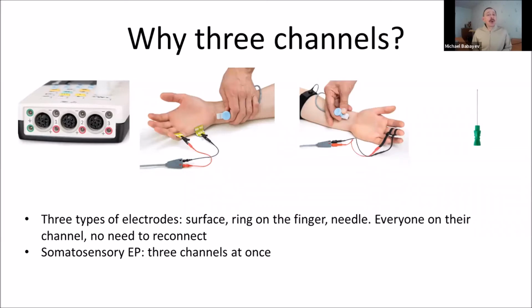And during one examination, usually the doctor needs to go from one type of electrodes to another. And if you, for example, have only 2 channels, it is necessary to reconnect cables during one examination. But here, when you have 3 channels and 3 cables, you can connect them forever. If you do only EMG examination, it is not necessary to reconnect. It is not time consuming.